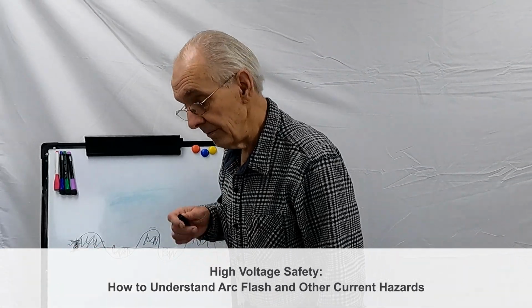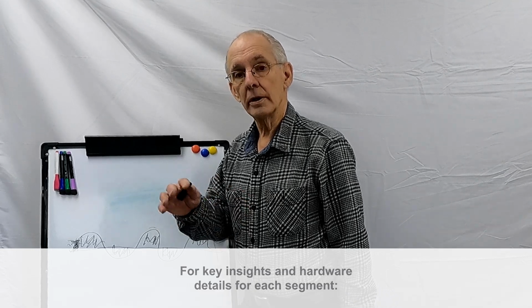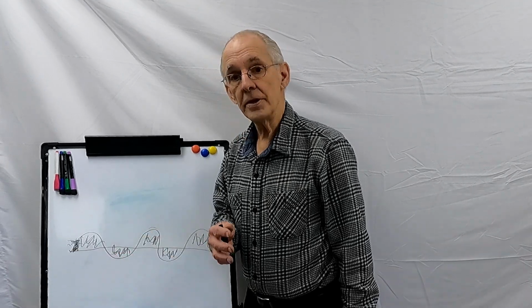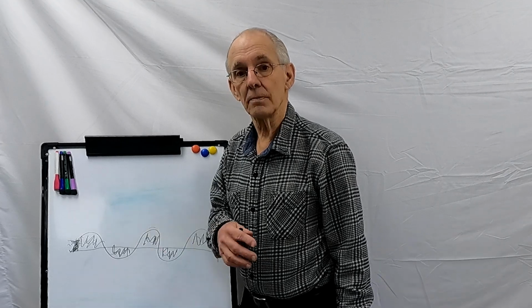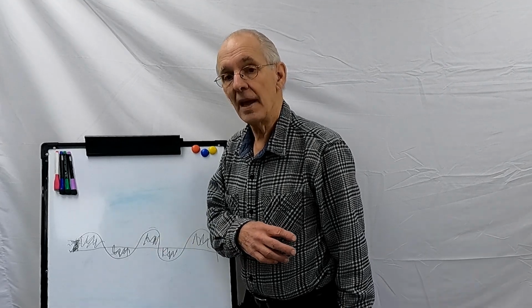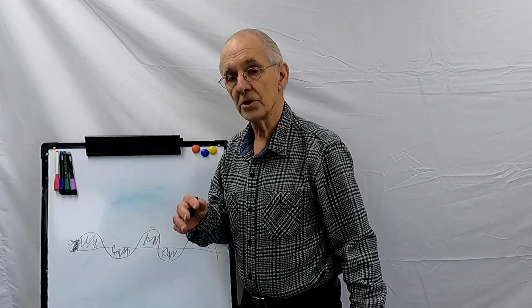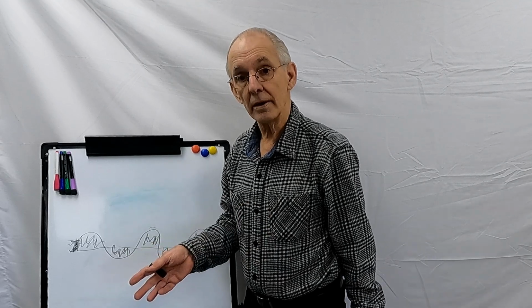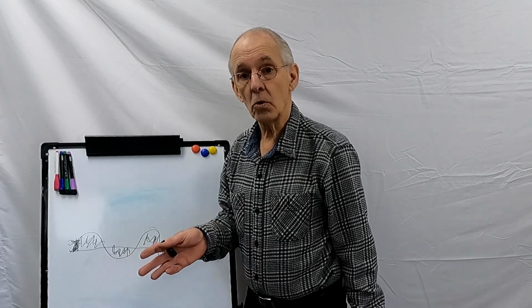Nowadays, when they design an industrial building with 480 volts, they're required to have an electrical engineer do a study of all the fault paths and what current levels can be generated, so they can properly size the fusing and so forth. That's a very complex process. They have to know everything about every panel, the size of every wire, the length of every wire. It's a big job, but it's now required.